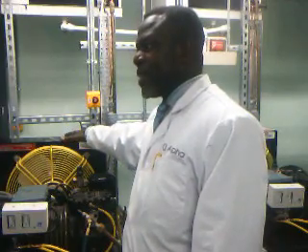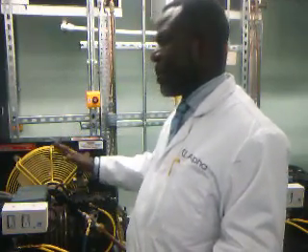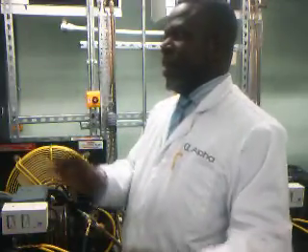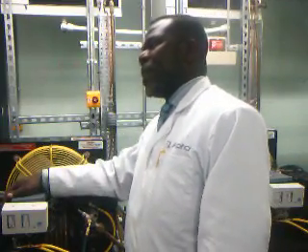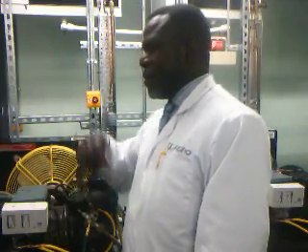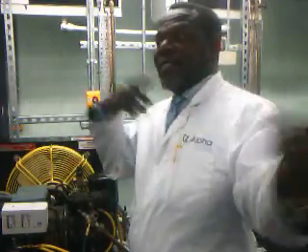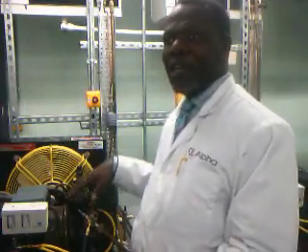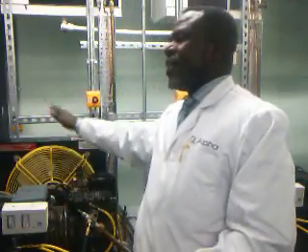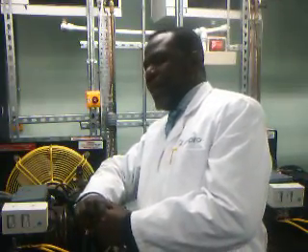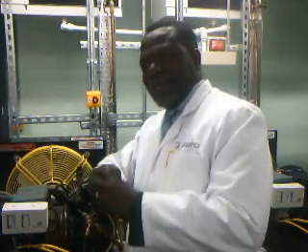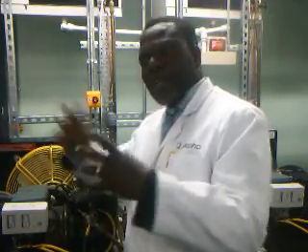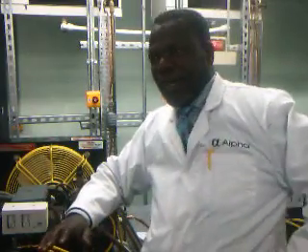When you calculate condenser capacity, it will be related to the heat load you use to calculate the compressor. So you end up getting the right capacity to match, because you are using the same factors. The factors you use to calculate the heat load, you use some of those to calculate the condenser capacity. So both of them must be the same factor, or can be different? They have to match. Condenser and compressor must match.